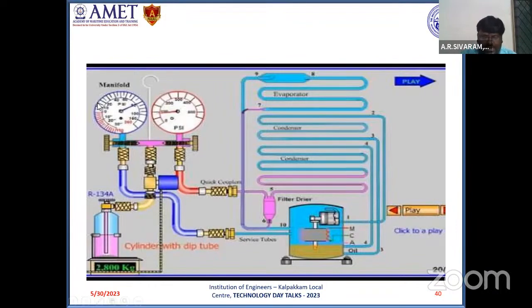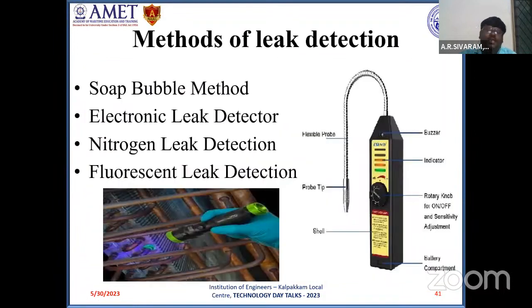Normally, the blue color indicates the suction gauge, and the red color indicates the gauge on the discharge side, or compressor outlet side. Now, methods of leak detection. In case a leak occurs in the system, in domestic refrigeration systems mechanics normally employ the soap bubble method. In commercial systems, we rely on an electronic leak detector.